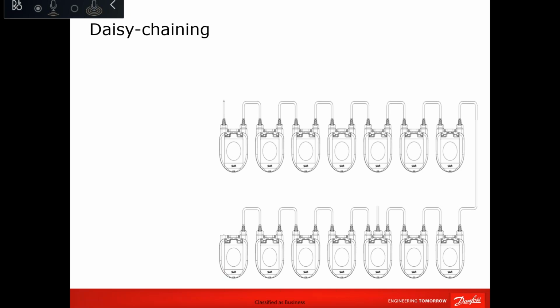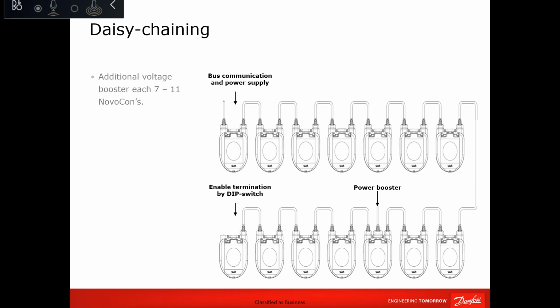So daisy chain, how will it look? As you can see, on the small actuator, Novocon S, you can loop together 64 actuators. In the medium size Novocon, you can loop 32. And in the large Novocon, Novocon L and XL, you can also loop 32. But if you are looping the Novocon with another BACnet device, because it's an addressable actuator, which means it can communicate with any existing addressable BACnet device, this will be counted in the loop. Let's say you are looping Novocon with DDC, another Novocon DDC, Novocon control, and so on, then the total loop will be 32 instead of 64.